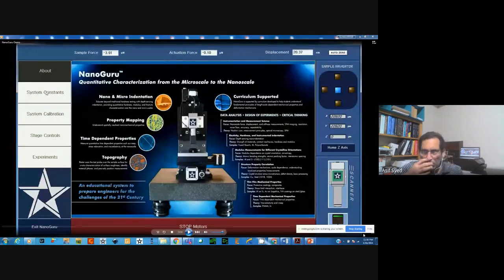If anybody has used the Hysitron system, they will see a big difference between that and this. The reason we built it this way is that it is very, very easy to use. You will see that in a few minutes. There are 3 counters here. The top 3 counters give you an indication of the sample force, the actuation force, and the displacement of the transducer. It gives you feedback on what is happening with the system, so that we keep an eye on these readings.